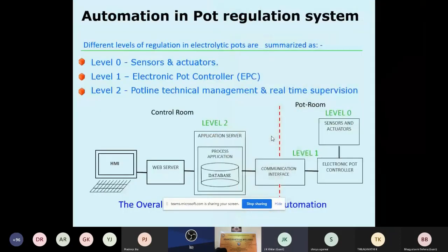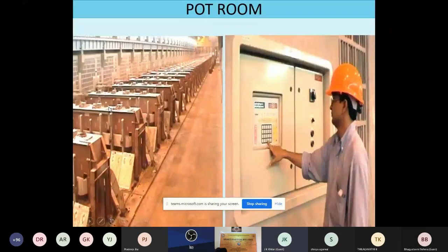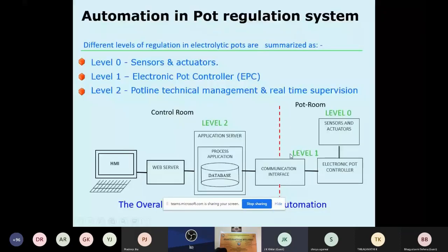Now in the automation of pot regulation systems, the sensors are at level 0, meaning the sensors and actuators are connected on the pot. Here we name them level 0 instruments. Then level 1 is the micropot, the electronic pot controller. By means of RS485 protocols, it goes to the server, and this server is a very high cost server, more than 100 crores.